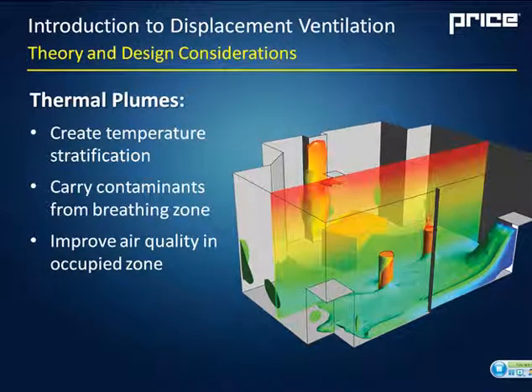Now, thermal plumes are something that's created when we allow free convection, and that just means we're allowing warm bodies to sit in the room, and we're allowing heat to rise off the top of their heads. That's the simplest way to put it. What they do is create temperature stratification. So as heat rises off the top of your head or off a piece of equipment or a computer, it rises straight up because it's less dense than the room air, and then it's stratified at the ceiling. And what that's also doing is carrying contaminants away from the breathing zone. So as you breathe out CO2 and other contaminants, it's going to be carried up in your warm breath as well as that thermal plume, and it's going to be carried to the ceiling and stratified there.